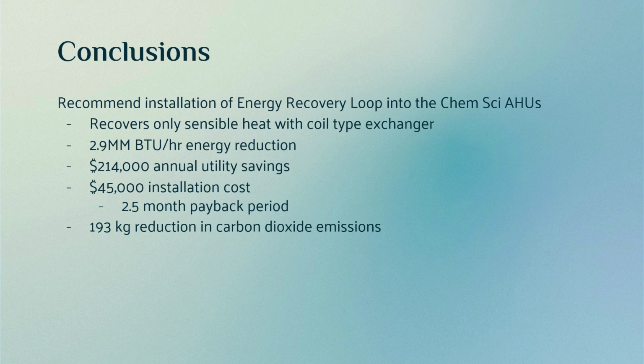This is able to reduce our energy by 2.9 million BTUs per hour, which equates to an annual utility savings of $214,000 a year. This is with a relatively low installation cost of $45,000, so we'd have a simple payback period of about 2.5 months. This system would also allow us to reduce our carbon emissions by about 193 kilograms annually. And with that, we will move on to our second project.